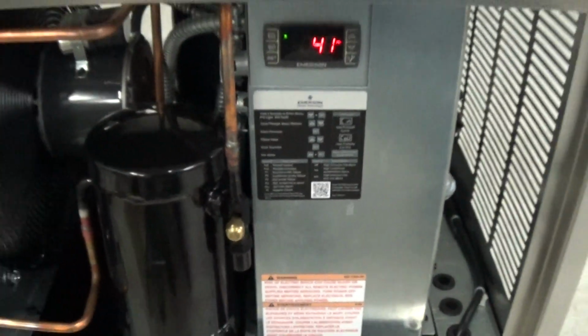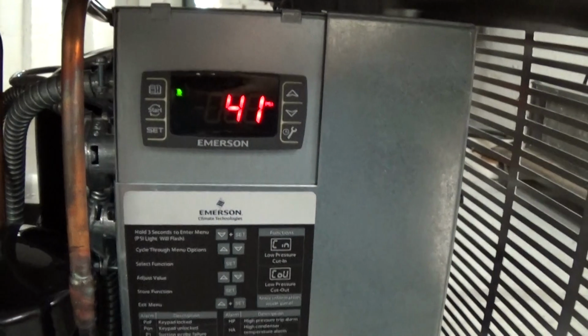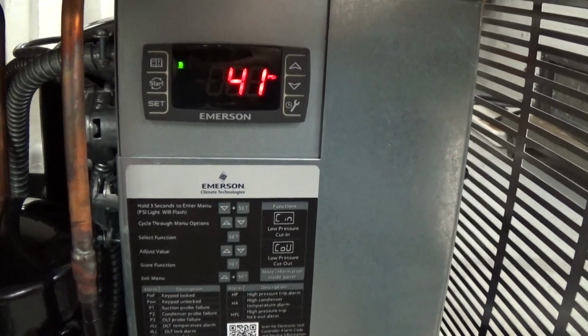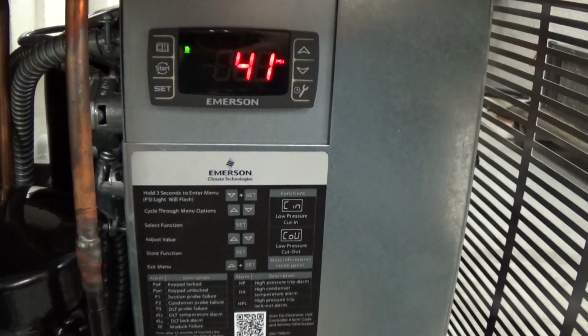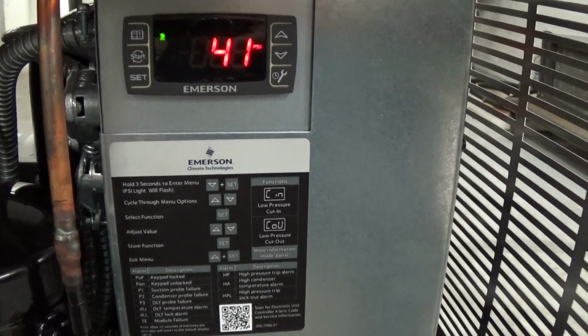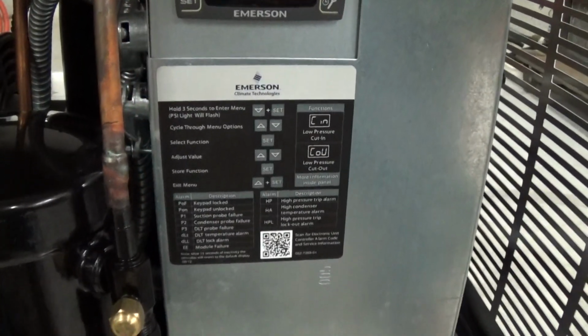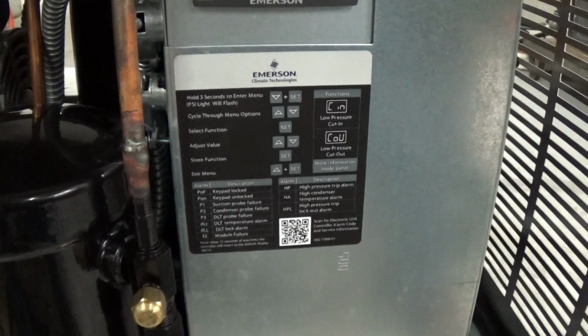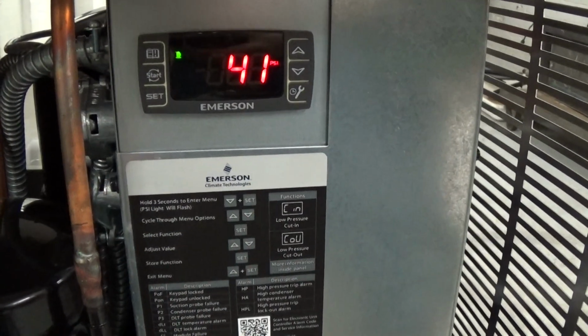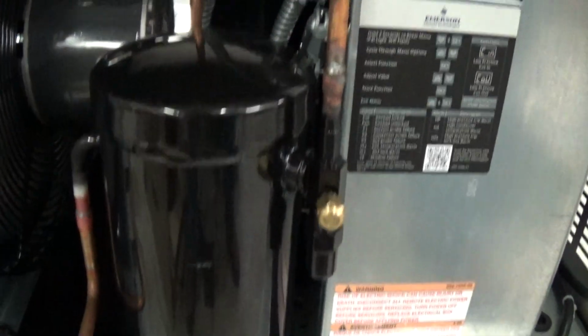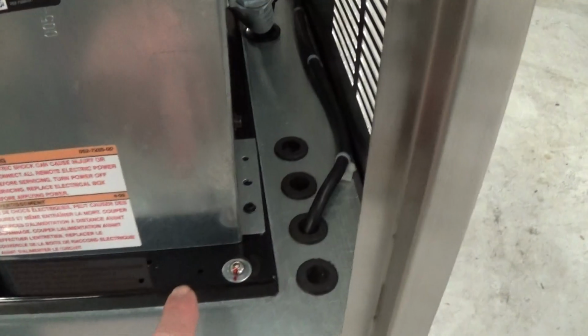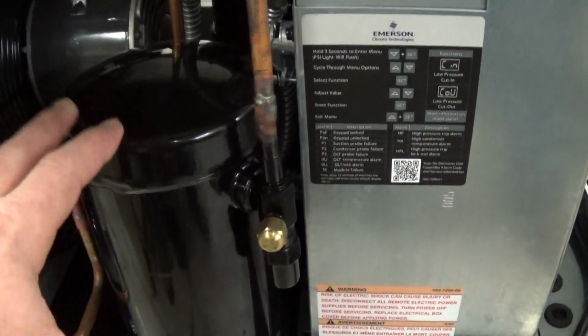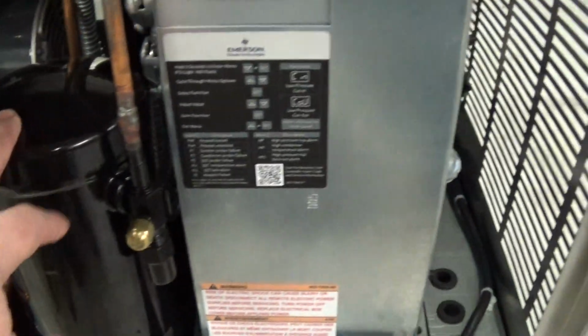The latest designs with compressors are kind of slick. This is the latest design, electronic. You don't need to touch anything internally here, but this allows an HVAC technician to change your high pressure and low pressure switches and some other alarms as related to the refrigerant circuit, not to be confused with any alarms on the fluid temperature. This is all strictly part of the refrigerant package.